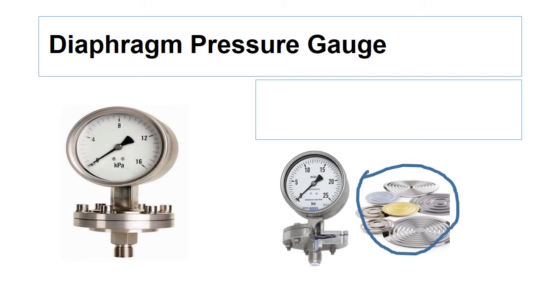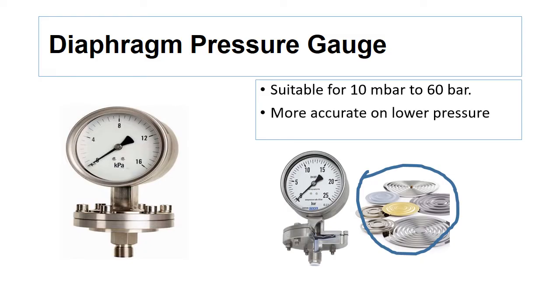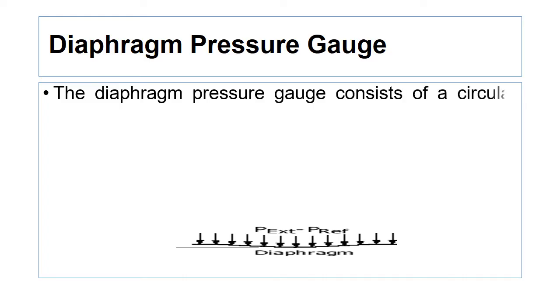The next pressure gauge is the diaphragm type pressure gauge. In this gauge, the measuring element is a diaphragm. Diaphragm type pressure gauges are suitable for a pressure range of 10 millibar to 60 bar. Diaphragm gauges are more accurate at lower pressures compared to Bourdon tube pressure gauges. The diaphragm pressure gauge consists of a circular membrane or diaphragm made from sheet metal of precise dimensions.